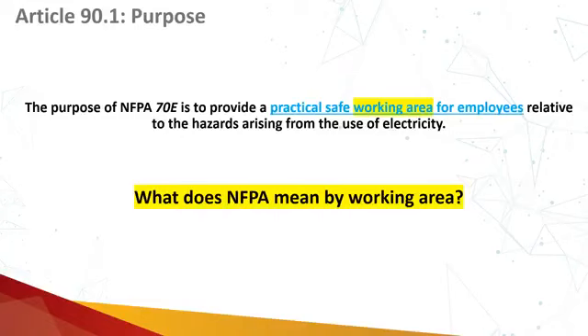And then we discussed the difference between the working area and what is covered in the working area. So if I'm standing in front of any printing machine and there is some panel behind that printer from which it is switched on and off, or there is a breaker there, that is not the working area. But if some problem has occurred, the printing machine is not working, and an electrician is going to come and open that panel in order to access the breaker, to check whether the breaker has tripped or melted, or some cable has become loose, or the breaker has become faulty, etc., now that area is converted into the working area.